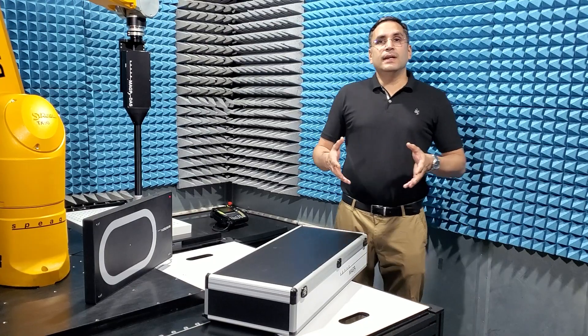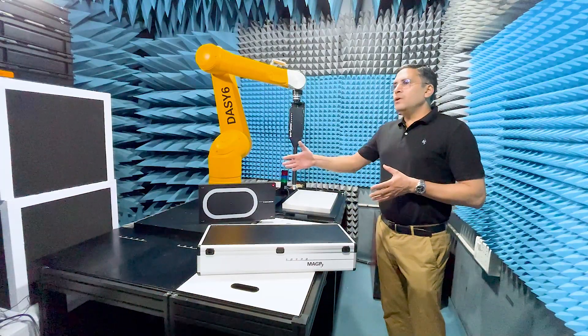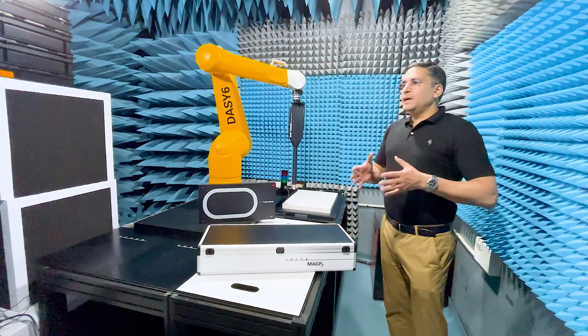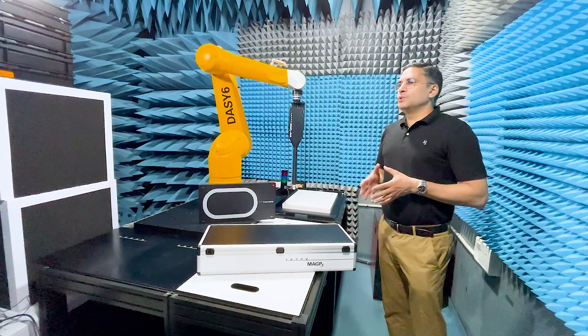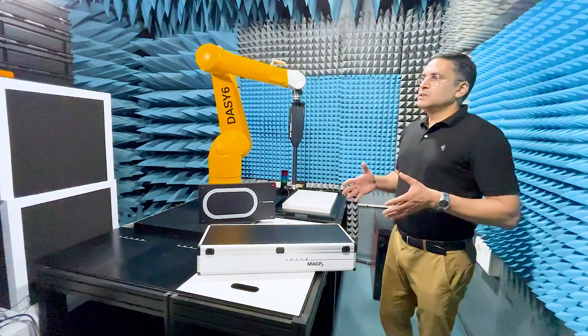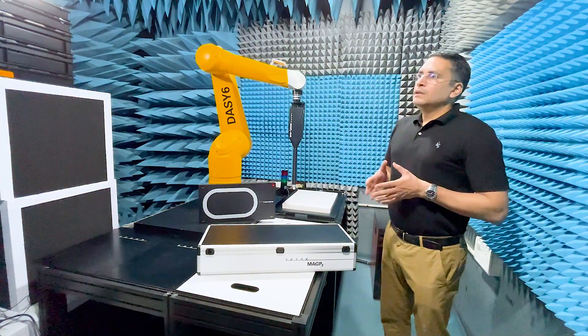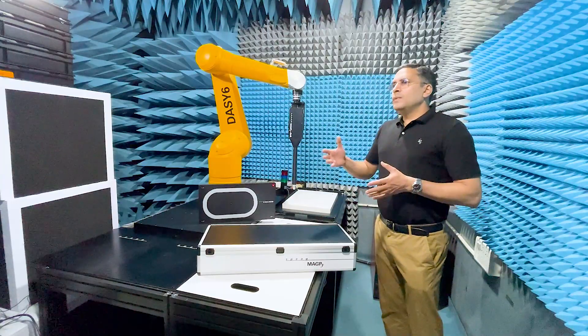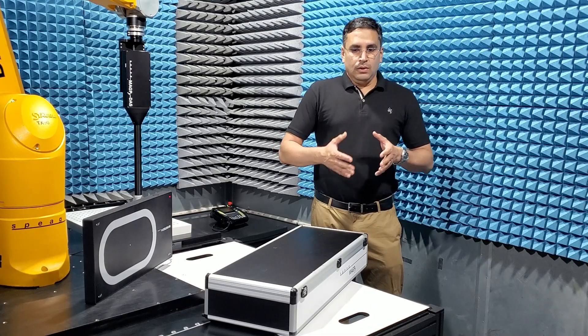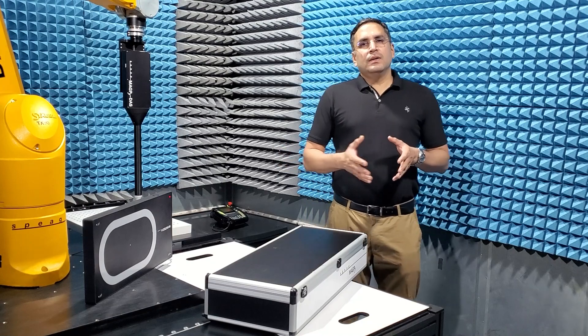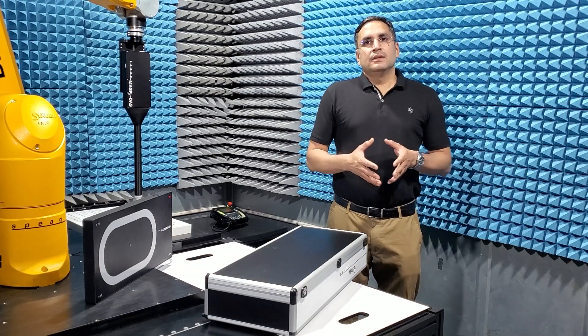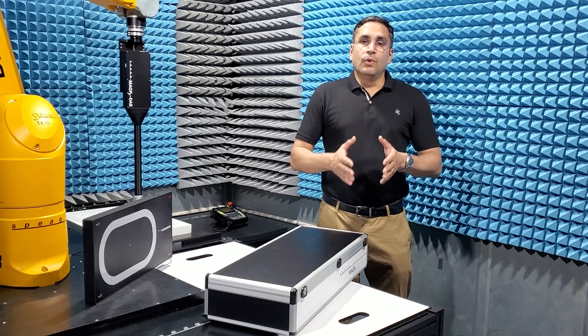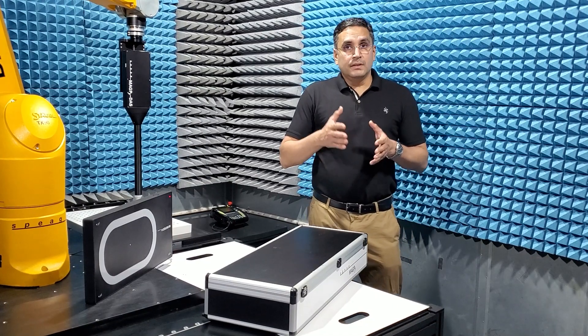I plan to test the device in more detail in follow-up videos. As you know, Magpie stands for Magnetic Amplitude and Gradient Probe System and it promises a lot more than any comparable electromagnetic exposure meter as it not only enables to demonstrate compliance with the field limits or reference limits of the various standards but much more importantly with the basic restrictions that are the limits for peak spatial specific absorption rate or SAR and induced E-fields or current density.